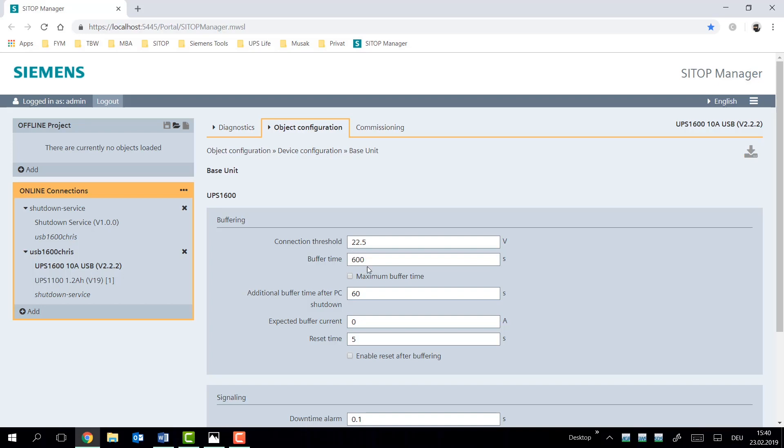For the other option, which is limiting the buffering time, this is for customers that have a shutdown procedure in place. Now, these customers are looking to bring their system into a known state, and if for some reason the shutdown procedure isn't successful, and by virtue of the power failure itself, then it's important there's only one option left, which is simply powering down the system. This has the secondary benefit, of course, of not unnecessarily depleting the batteries.